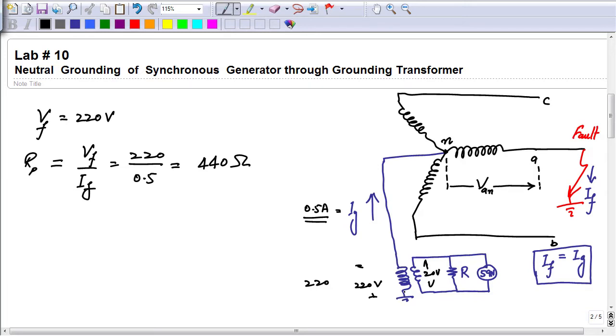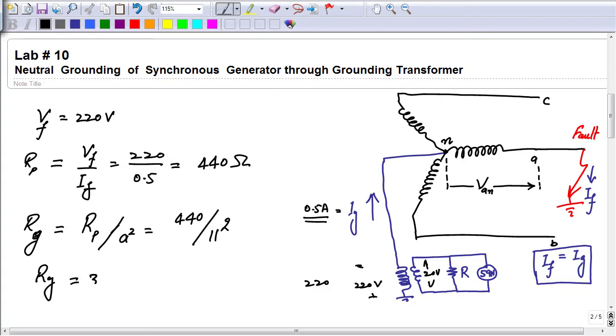But here we have used a grounding transformer, so the impedance will be connected on the secondary side of this transformer. Our resistance is going to be connected on the secondary side of this step down transformer. So the resistance on the secondary side that is to be inserted, we call it Rg, is equal to the primary resistance divided by the square of the turn ratio. So that would be 440 divided by 11 squared. If we solve this, the Rg value will be 3.64 ohm. So this is our calculated value of Rg.